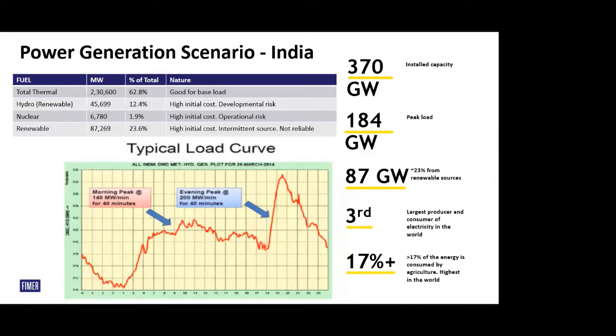So we usually hear the power operators saying that we have tuned our generators for this ramp and things like that. One of the notable incidents was when our honorable PM announced that you have to switch off lights. The operators were telling people, don't switch off everything, just switch off the light loads, don't switch off the other loads, because it can drastically affect the grid. We'll see that in the later part.